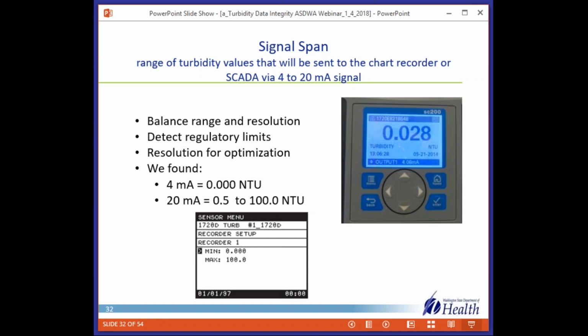So here's what we found. All of our plants had the lower level set at 0, so 4 milliamps set at 0. But there was actually a huge range in the upper limit, and these were all for finished water turbidimeters, everything from 0.5 to 100 NTU. Which is not much of a filter.